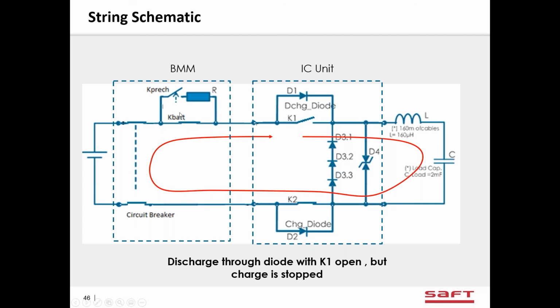We have a pre-charge circuit if necessary to charge any external capacitors before we close our contactors. And then in the IntelliConnect unit, we have these 2 contactors, K1 and K2. In some cases, we do not use K2, but let's talk about K1. You can see that the battery is discharging, the red arrow is discharging into the load, and I wish the arrow went up through the diode, but you can see the contactor is open.